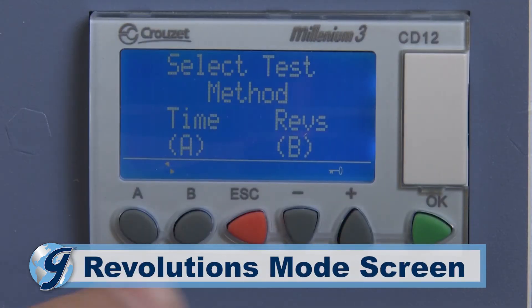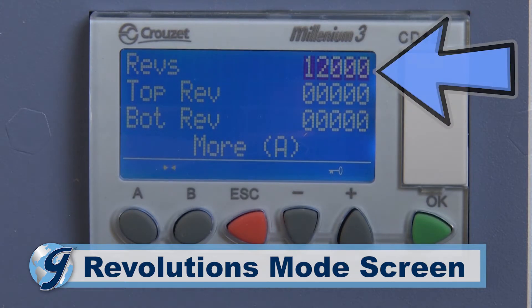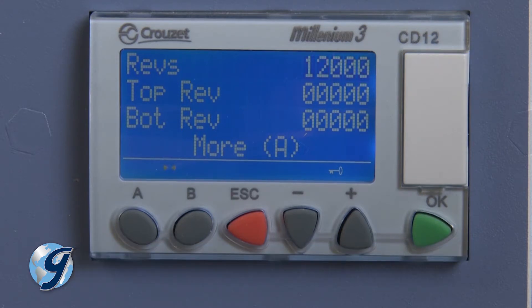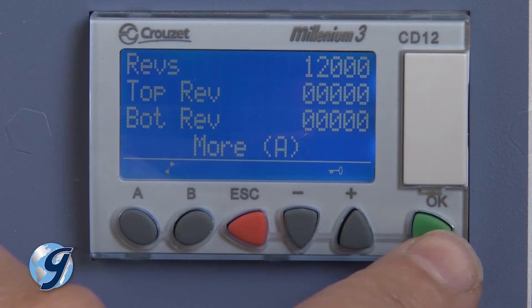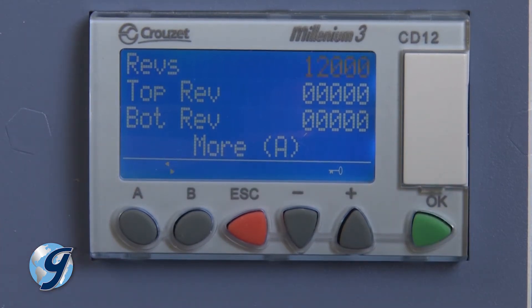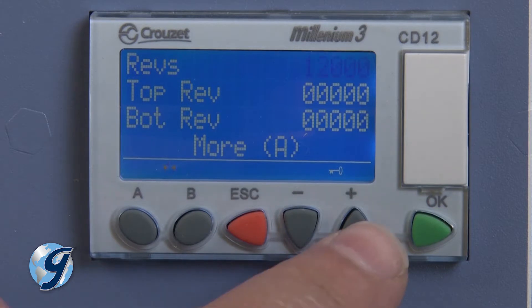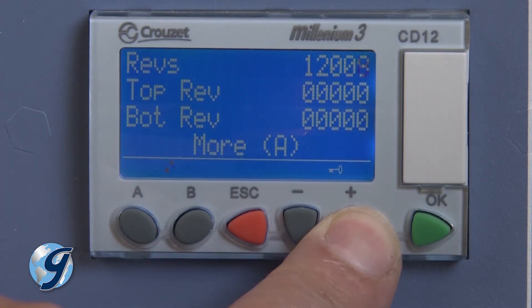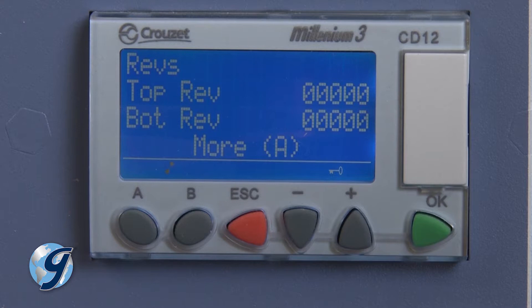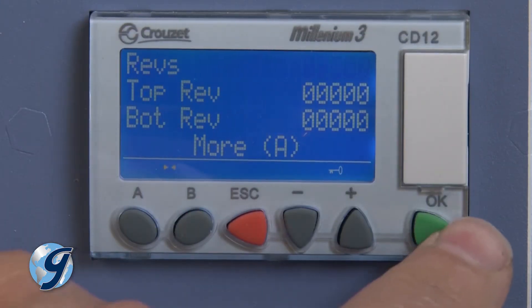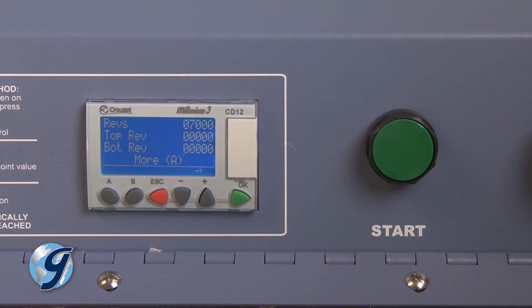In selecting the revolutions mode, the revolutions or REVS line will indicate the set point for the maximum number of jar revolutions during the test. To change the set point, press OK and the revolutions value will begin to flash. Adjust the set point using the plus or minus buttons; as the buttons are held down, the rate of change will become faster. Once the desired value is displayed, press OK to save. Now you are ready to begin your test. The next two lines display current test revolutions for the top and bottom jars and are updated every second.